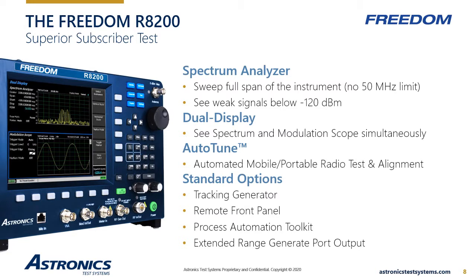The Freedom R8200 is a high-performance instrument with features and specifications to prove it. Sweep the RF spectrum as wide as you want, no limits, and find those weak signals with a noise floor down to -140 dBm. Keep an eye on the RF spectrum and modulation at the same time. The dual display gives you simultaneous views of the frequency and time domains. Drastically cut down time required to test and align subscriber radios. AutoTune automates the process reliably and repeatably. Free your technicians to do other work.